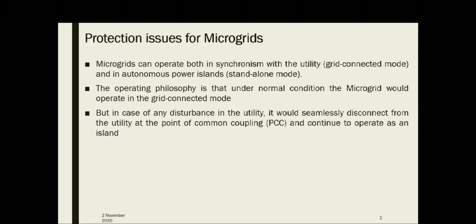So the operating philosophy is that under normal condition the microgrid would operate in the grid connected mode, but in case of any disturbance in the utility, it would seamlessly disconnect from the utility at the point of common coupling and continue to operate as an island.